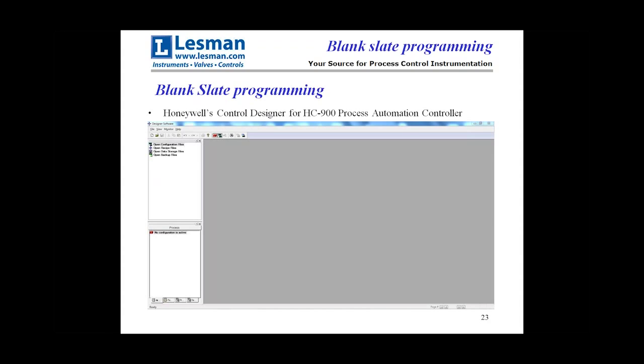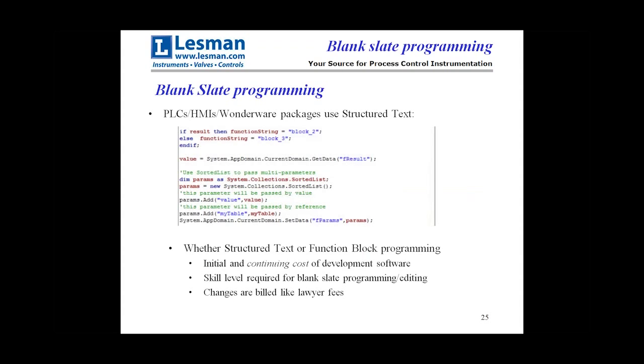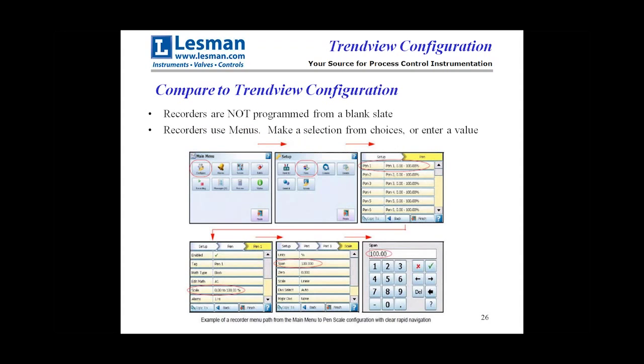Here's an example of blank-slate programming from our process automation controller, the Honeywell HC900. When you open up the software, you see a blank slate — nothing on it. You have to put everything there yourself, placing function blocks, labeling tags, configuring them. The other form of blank-slate programming is structured text — the if/then/else kind where you have to know dimensions, syntax, and if you use a colon instead of a semicolon it won't compile. In the HMI/PLC world, a lot of times it's structured text. The point is: it's programming compared to configuration.